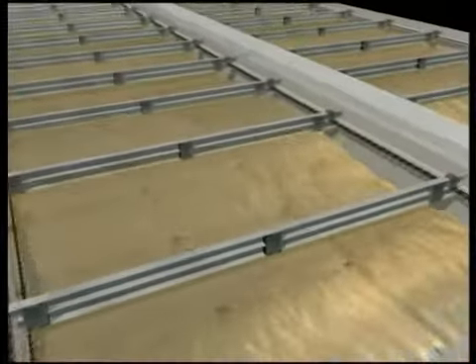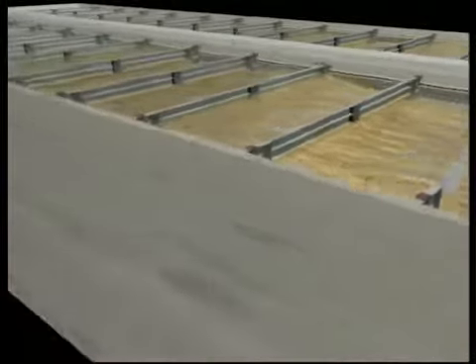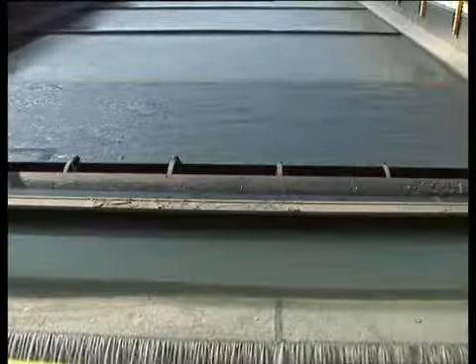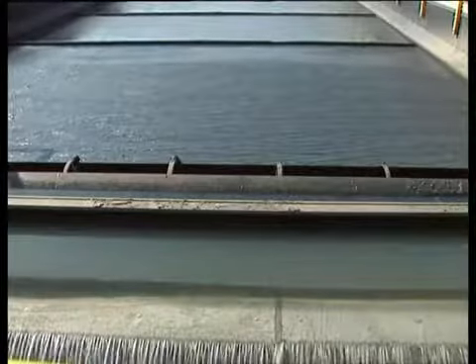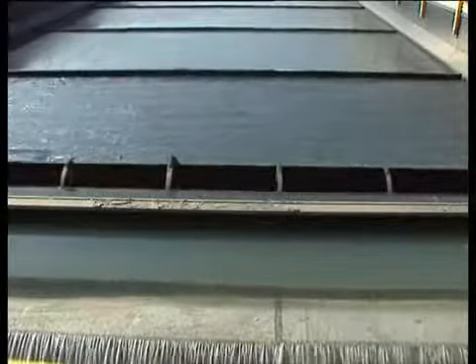Given the large flow of throughput, double sedimentation tanks have been installed at the plant to reduce the space required for the sedimentation process. In total, the sewage remains in the sedimentation tanks for about 1.5 hours, allowing the suspended matter to settle. These solids, called sludge, are then removed and pumped to the holding tanks at the sludge dewatering facilities.